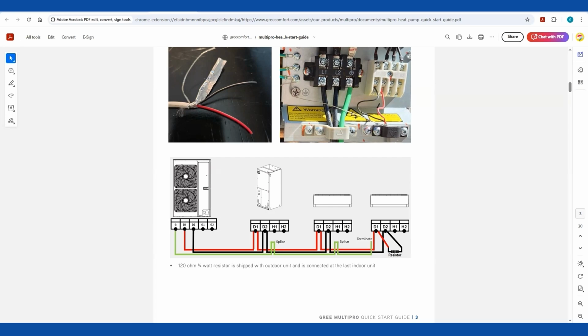Then we do show you the end line resistor on D1 and D2. This is shipped in the outdoor unit. It's a 1/4 watt, 120 ohm. It says it right here on the quick start guide in case you guys forget. We do not source these, so be very careful when you're installing these units. That comes shipped in the bag in the outdoor unit. Please don't throw it away.